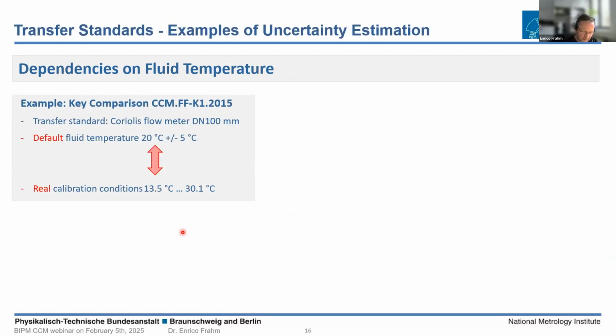So the first example deals with the temperature sensitivity of a Coriolis flow meter used in a comparison. The motivation for the research was the observed discrepancy between the default temperature given in the technical protocol of the comparison and the real fluid temperatures during the calibrations of the participants. So the question was, is the fluid temperature significantly different between the laboratories? What does it mean to the meter characteristics?